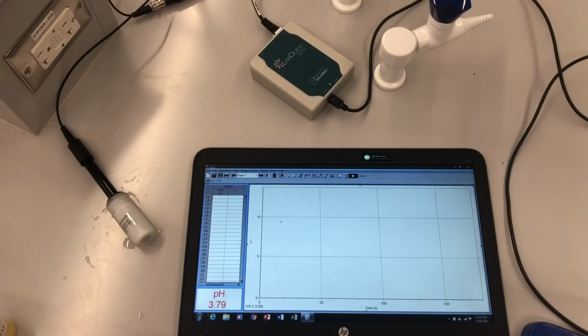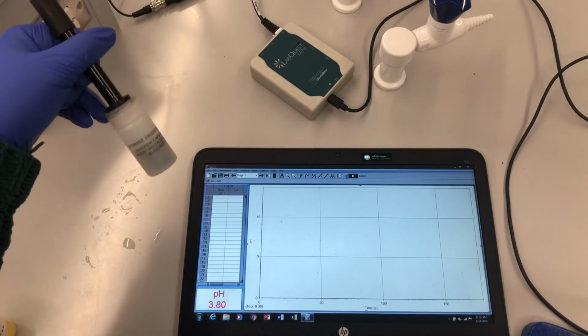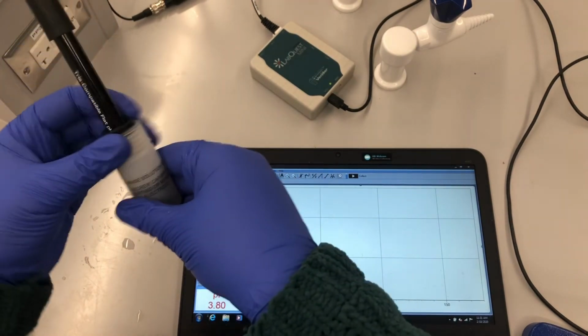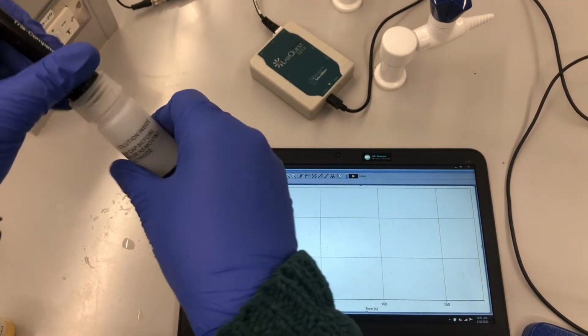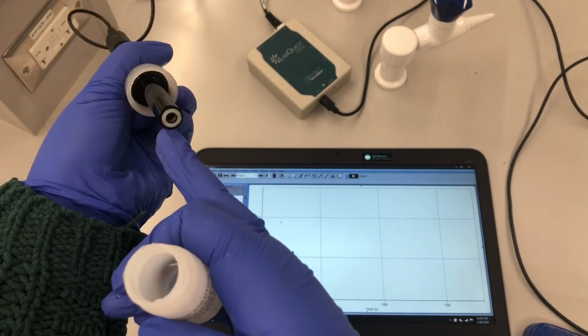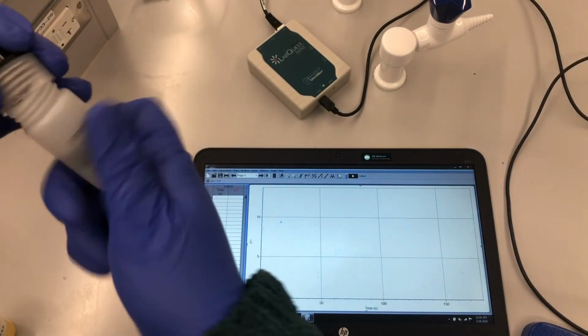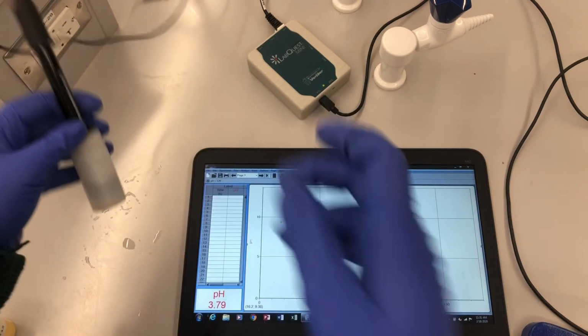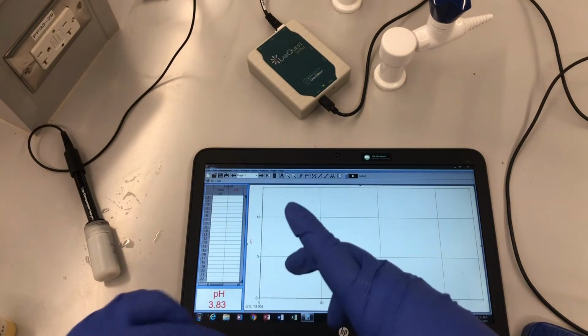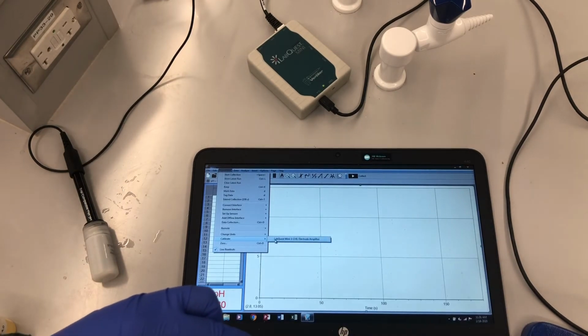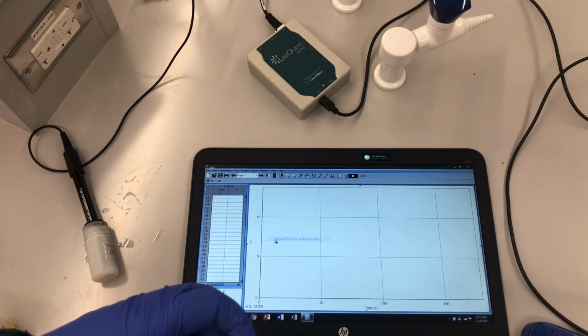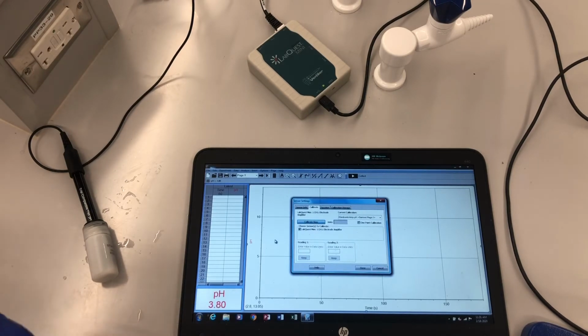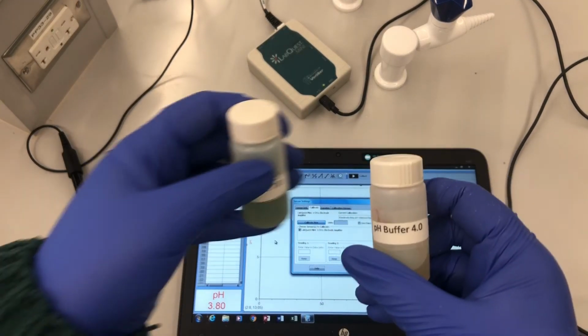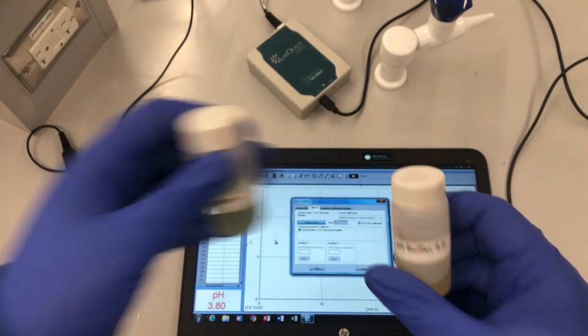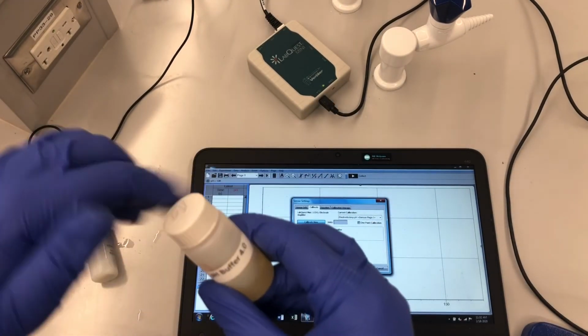To measure pH, we do it in a very similar way. This is the pH probe. It's always kept in a storage solution because we never want it to dry out. And it measures right down here at the bottom. So we're going to start by going to Experiment, Calibrate, and going to the electrode amplifier. Now our two standards are a pH 4 buffer and a pH 7 buffer. So I'm going to start with the pH 4.